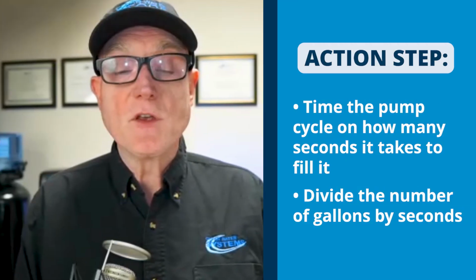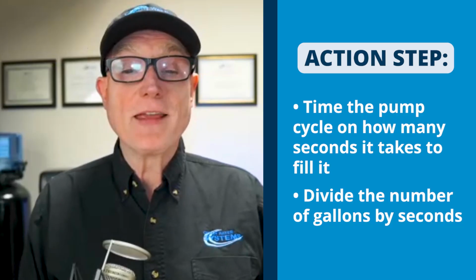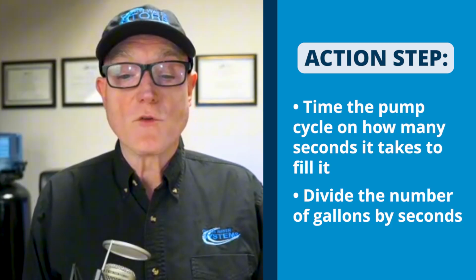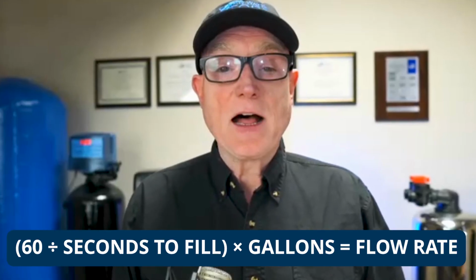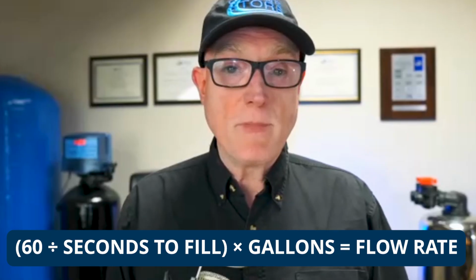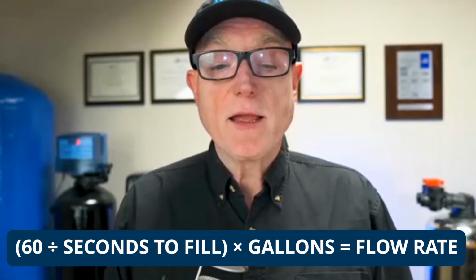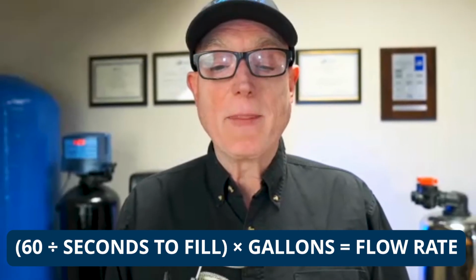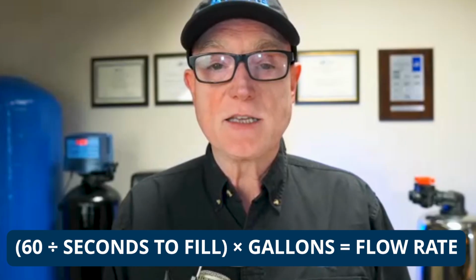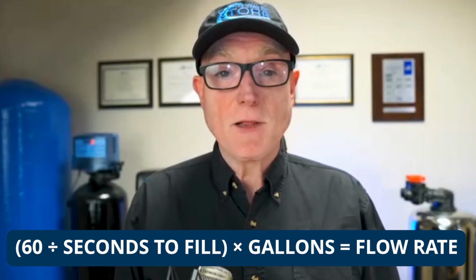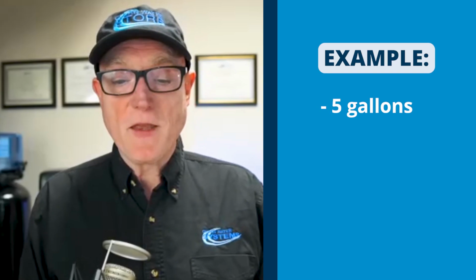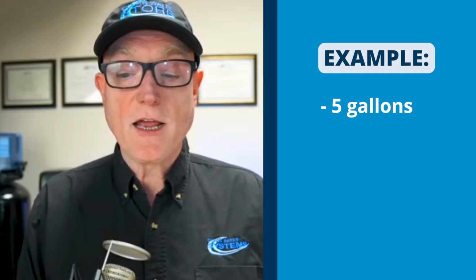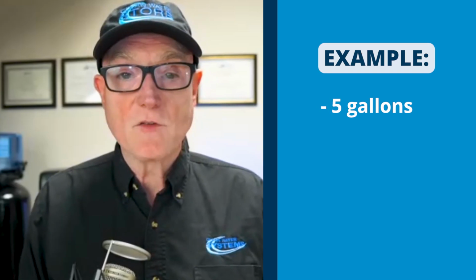The next step is you want to divide the number of gallons by seconds. So for instance, you take the gallons that you measured in step 3 and you divide that by the number of seconds in step 4. And then the final thing is you multiply it by 60. So here's an example. Say the number of gallons collected during drawdown of your pressure tank was 5 gallons, which is not unusual.